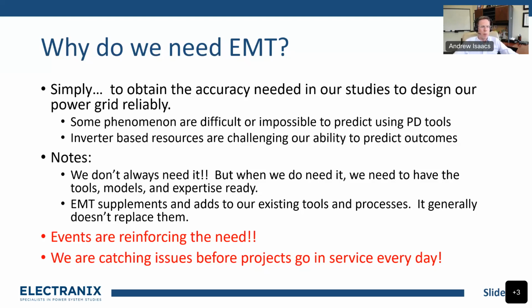I would add a little more weight to that. Recent times -- and actually you can find recommendations like this from NERC going back quite a long way, five years at least and more -- I think the 2017 one is probably no longer available because NERC takes them off after a while, but this is a recent one that says EMT models should be required for all newly connecting BPS connected inverter-based resources. Now, this isn't saying you must do a study every time, but it is saying you need to collect the models, because once the interconnection has happened, it can be very difficult to go back and get those models. If you look at the recently published IEEE standard 2800, which is interconnection for IBRs, it also has, in the normative text, chapter 10, that upon request from the transmission operator, the IBR owner will provide an EMT model.